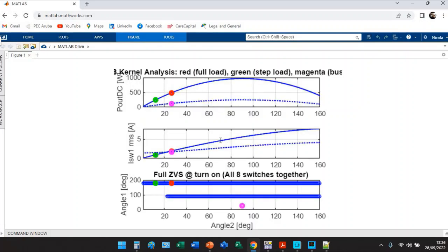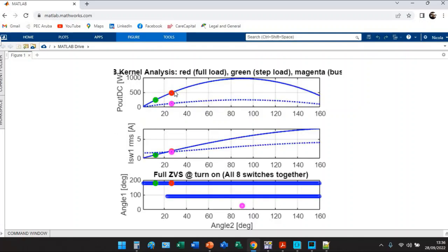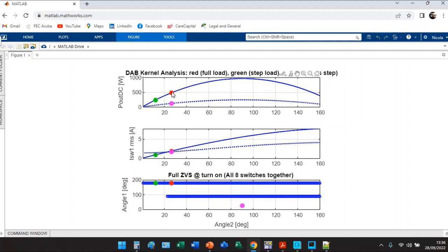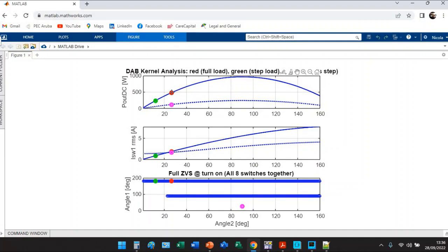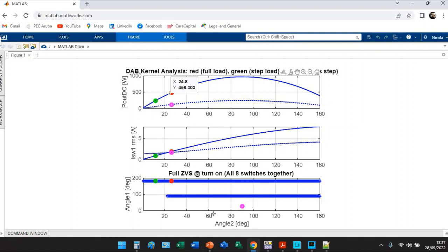At full load we are operating in this point here in which we have angle one equal to 180, angle two equal to 26 degrees approximately. When you gave the step load, here I considered the same case as the webinar with half power step load. You are moving from the red bullet to the green bullet, so angle 2 is reducing from 26 to something like 12.